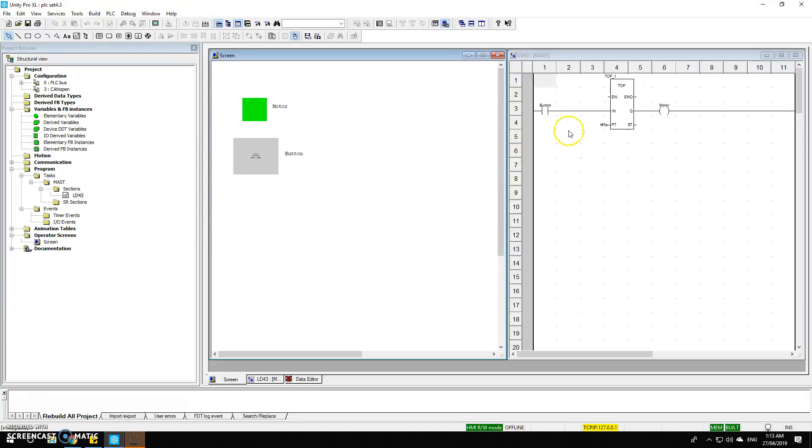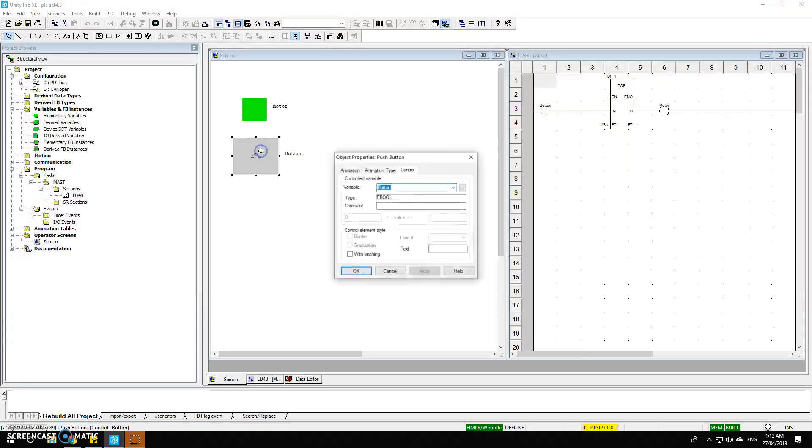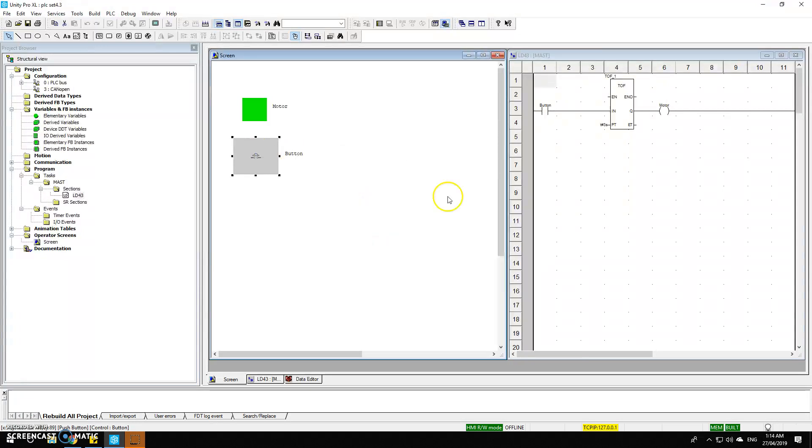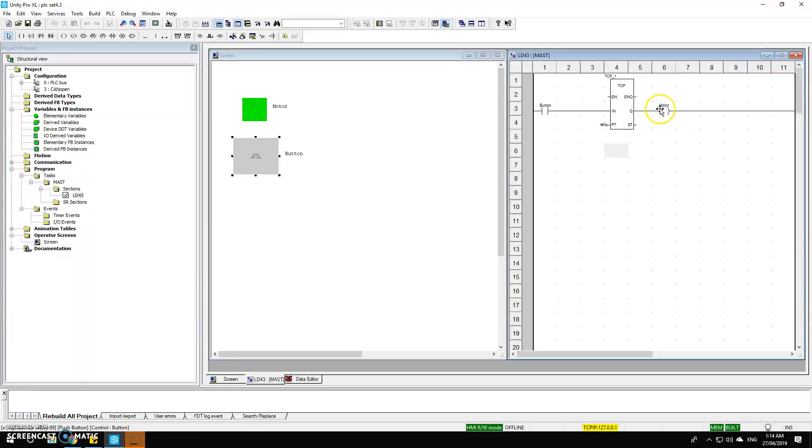This is the LD program to turn off the motor automatically after 3 seconds. The input for the whole system is the button, which will be controlled by this button here. The input is going to be the input for the time-off function block with the preset time of 3 seconds, and the output coil represents the motor.